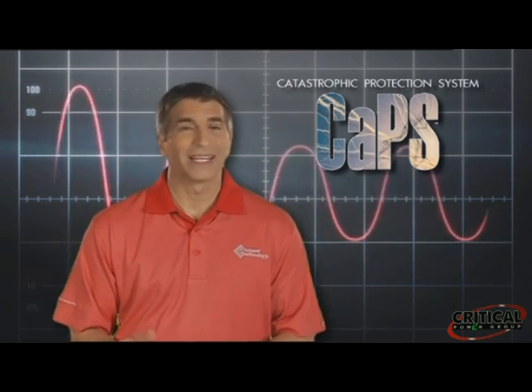By combining MOVs and selenium cells in a hybrid protection system, CAPS provides protection from power quality events from multiple cycles up to seconds, significantly longer than any MOV-based protection devices. This seemingly small amount of time is like an eternity to equipment loads when they're stressed by power quality events. CAPS protects against transient surges and also effectively diverts to ground the dangerous currents caused by TOV events. We'll demonstrate how in our next segment.